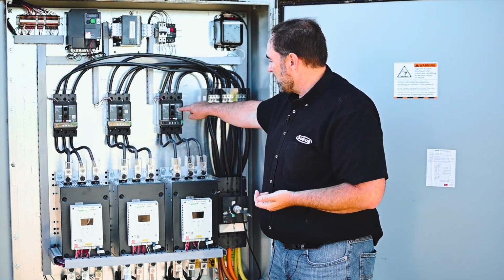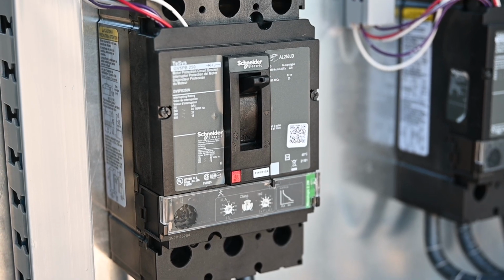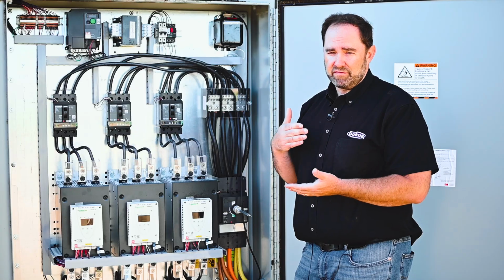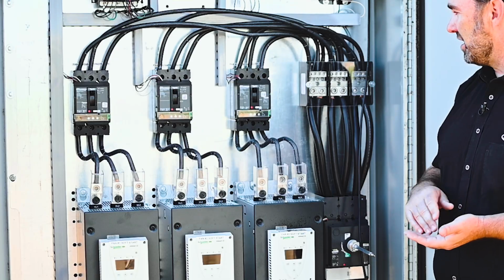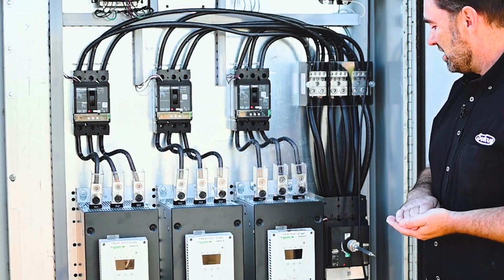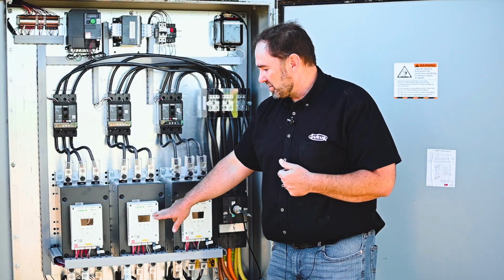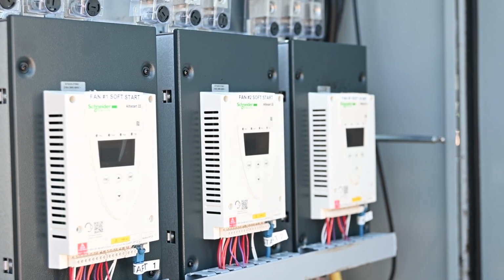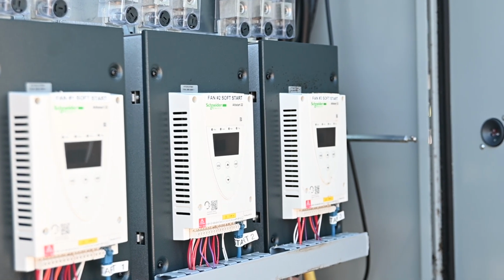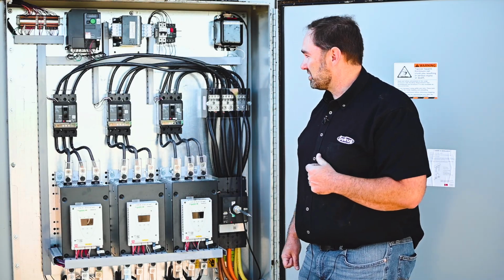You'll see we have, in this case, this is a 3-fan tower dryer, so there are 3 soft starts. Ahead of that, we have 3 breakers, and if there was ever a problem, the touchscreen would tell you if there was an overload on one of the fans, and that's going to be what that breaker is. The touchscreen would also tell you if there was a problem with the soft start. And remember, you don't have to get in this side of the cabinet to see the soft start display. We have the remote displays in the left side of the cabinet.